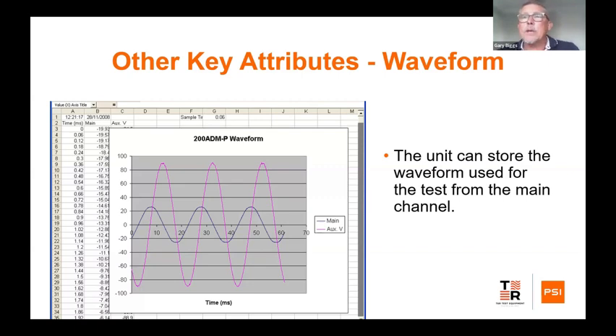Now that could be because you've got a relay where the burden's high and it's deforming the waveform, or it could be that whatever power supply is feeding the substation could be interfered with, typically in modern times, with harmonics. And again, not that we're here to talk about harmonics, but I'm sure all of the electrical engineers out there will be aware that harmonics are a big modern problem in a lot of situations. So if you've got a substation feeding, for example, a welding factory, you can pretty much guarantee that there's going to be effects on the waveform.